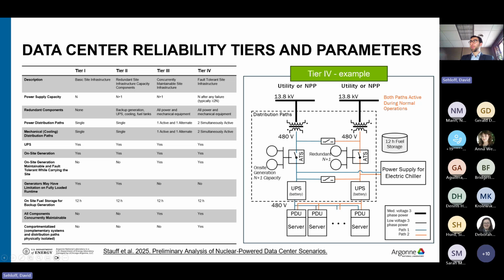Looking at what the topology might look like for different reliability tiers. I won't dwell on this—it's also in the report and in the uptime tier guide. But if we're looking at a highly reliable tier 4 type of data center, we are looking at 2 independent distribution paths that are active at all times, and that often includes redundant generation in each path, so there is a high degree of generation on site for these highly reliable data centers. Whether the generation comes from the utility or from the on-site generation is really an economic decision from the data center perspective.